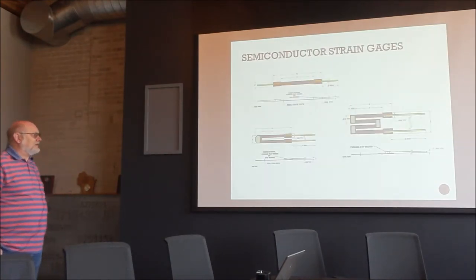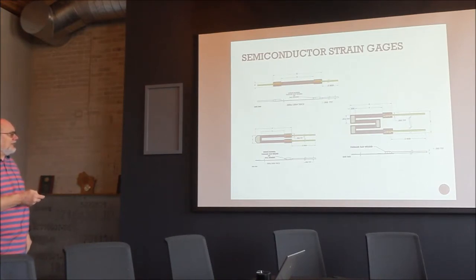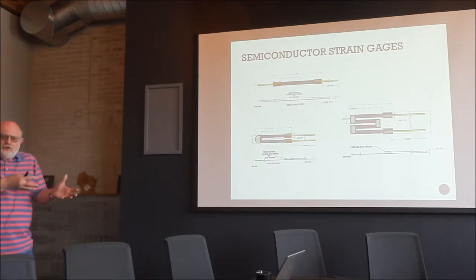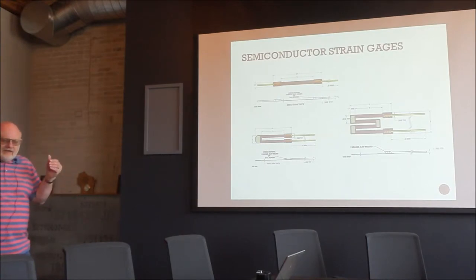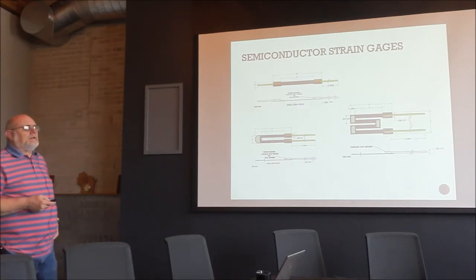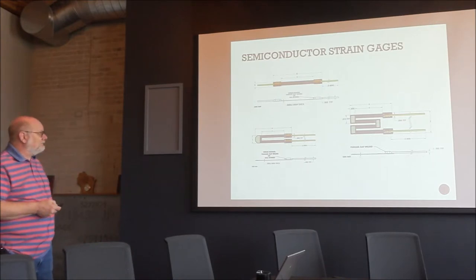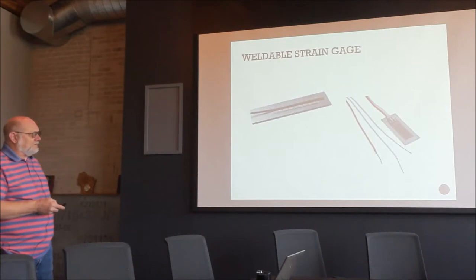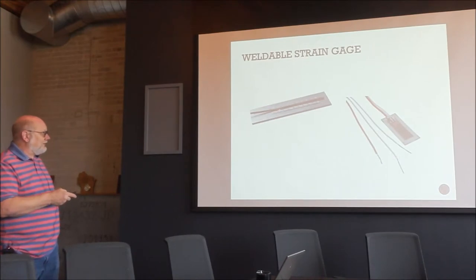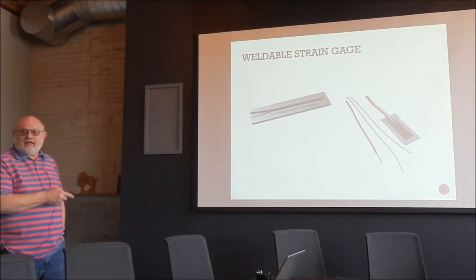Semiconductor gauges are just what they sound like — semiconductor elements with piezo-resistive properties, making them extremely sensitive. While a foil gauge has a gauge factor of two, semiconductor gauges can have gauge factors of 100 to 1000. The downside is instability and white noise — they're overly sensitive and require excellent instrumentation. Weldable gauges use foil or wire embedded in shim stock that can be spot-welded to the surface, though the standoff distance creates a strain transfer issue, especially in bending.